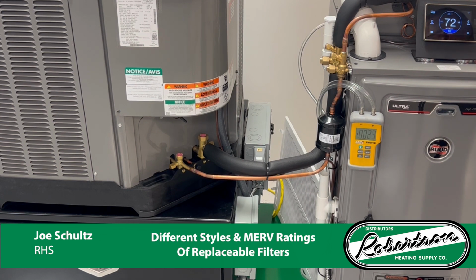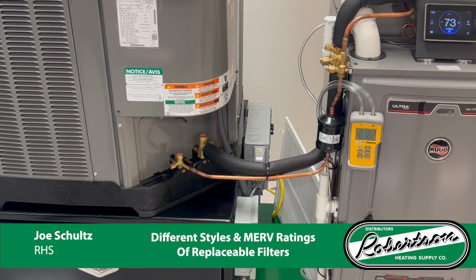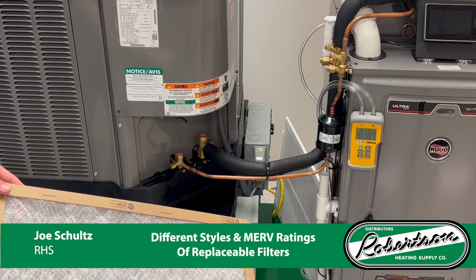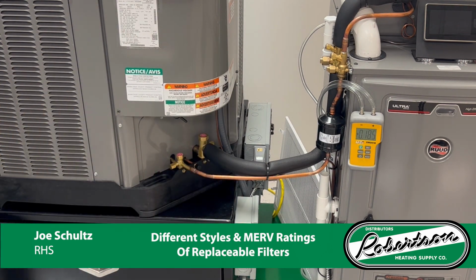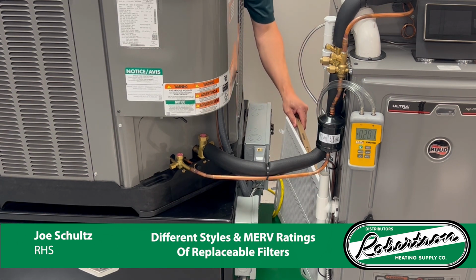And we're going to get a baseline number here. So we're getting a baseline number about 0.18 total external static pressure. That's with no filter on it. So the first filter we're going to try is this fiberglass filter. So it's our standard filter that most people use in the system.